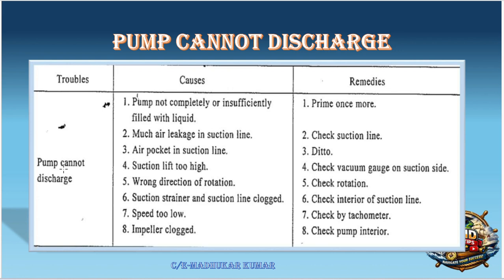Pump cannot discharge. This is the case. Means there is no discharge pressure and all. Okay. So you can see that the pump is not completely or insufficiently filled with the liquid. So this is the case. You need to prime the pump. Okay. So we know priming is basically the removal of air and filling up with the water. So if the impeller is completely submerged, no problem. Much air leakage in the suction line.